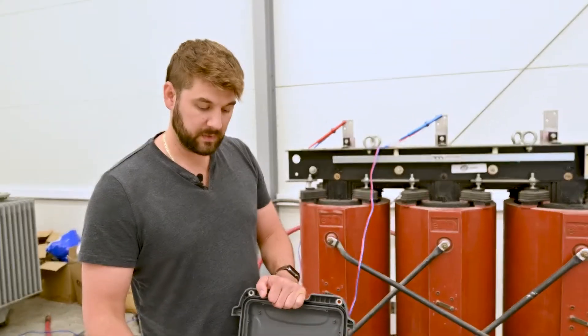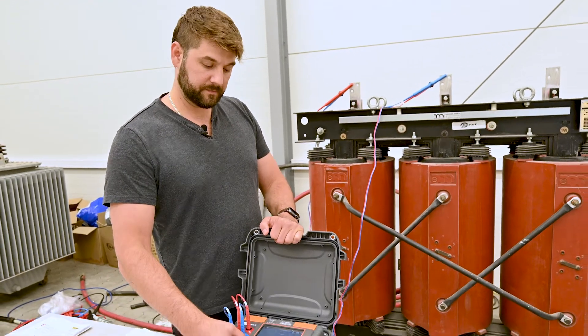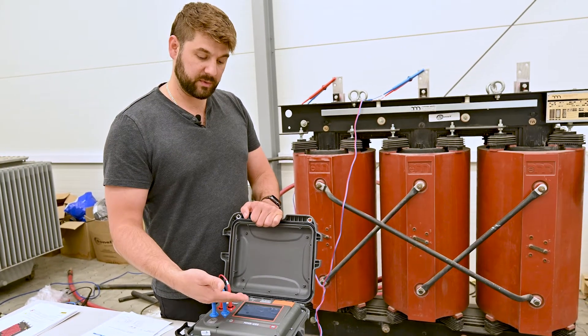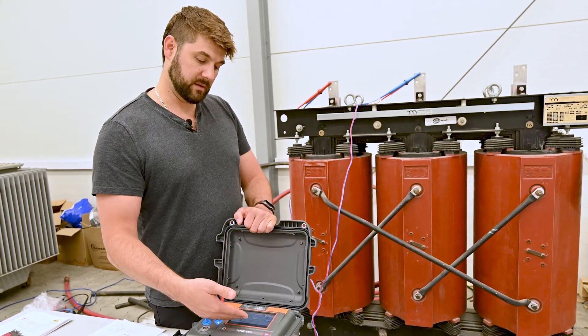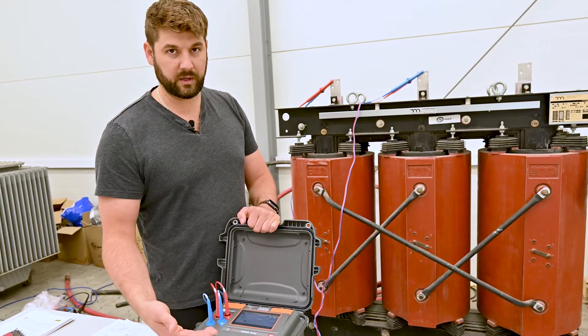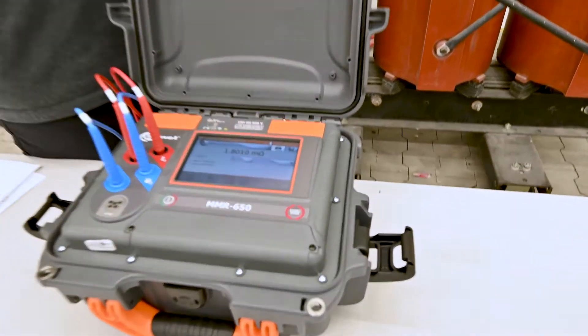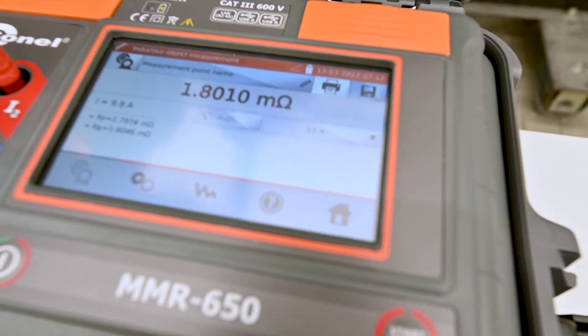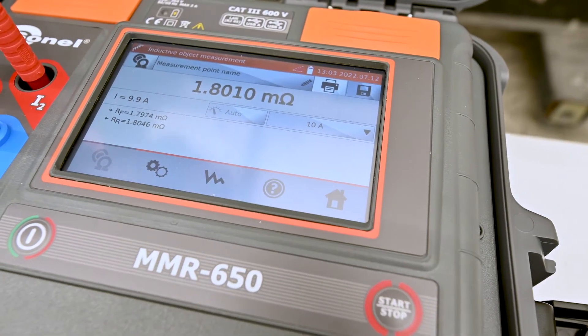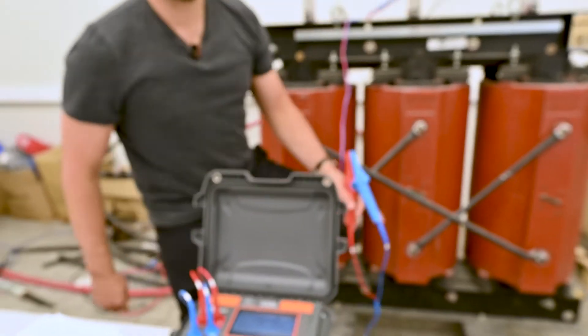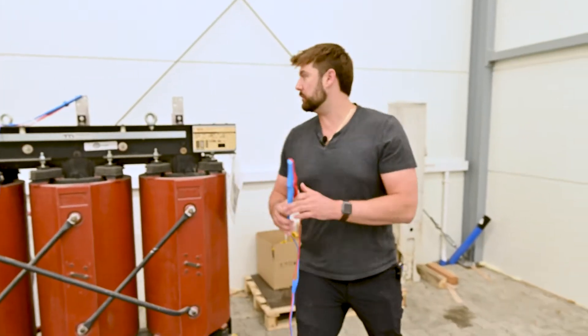Now that the measurement's been completed, the instrument's going to go ahead and automatically discharge. Now that it's beeped, we know that it's done and our final result is 1.801. Going to the other winding.